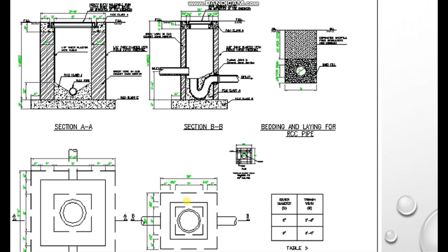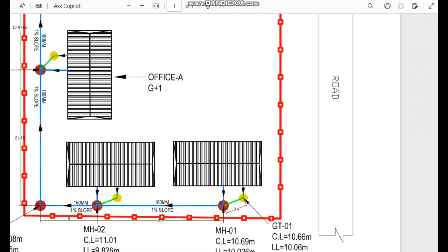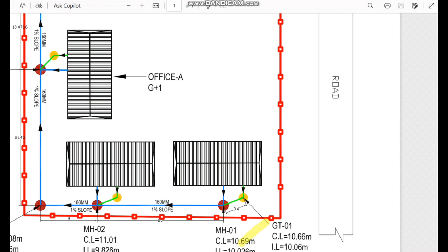This image shows the top view and section view of the gully trap. There is an inlet pipe and an outlet pipe, and between them there is a small gap — the inlet and outlet pipes are not directly connected. If we don't have this gully trap and the water from the wash basin is directly connected to the manhole, which also receives the connection from the water closet, there is a chance that the foul smell or sewer smell will go back to the kitchen sink, wash basin, and sanitary fixtures. That is why we provide the gully trap — the air gap acts as a water seal to arrest foul or sewer odors.